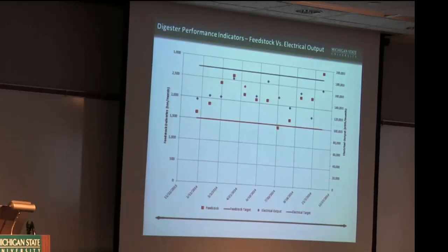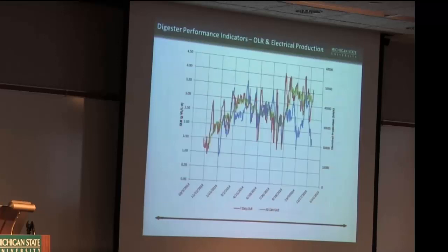The system is working well. The digester itself is performing extremely well. The methane concentration of our biogas is always 63 to 65%, which is very high compared to a typical dairy digester, which would run 52 to 55%. So we're doing very well overall. We've got the mechanical issues being resolved, and we're working out the feedstock deliveries and the feedstock energy densities.